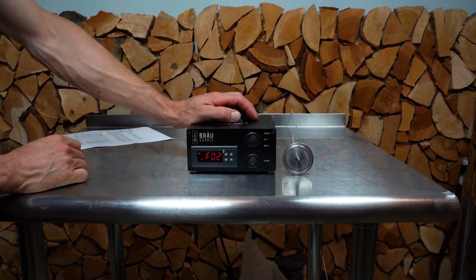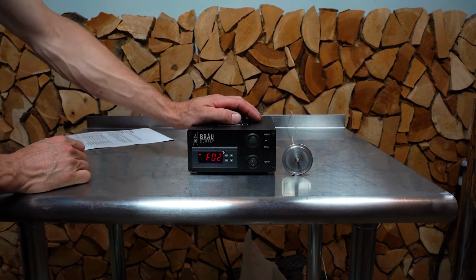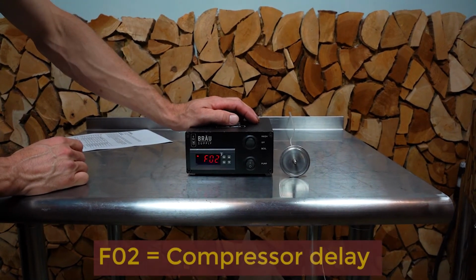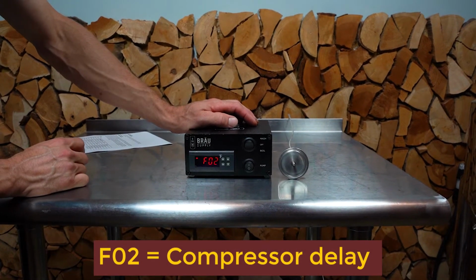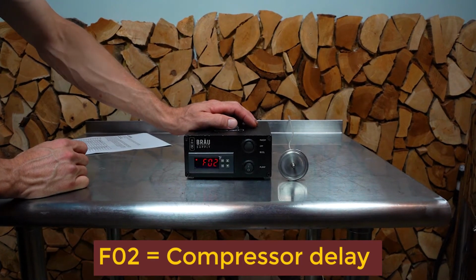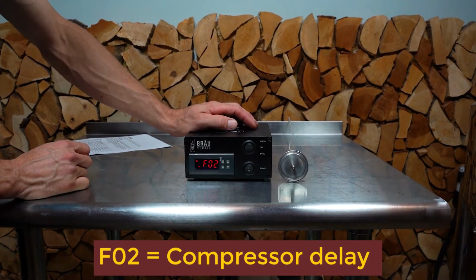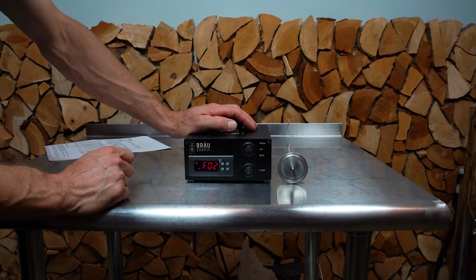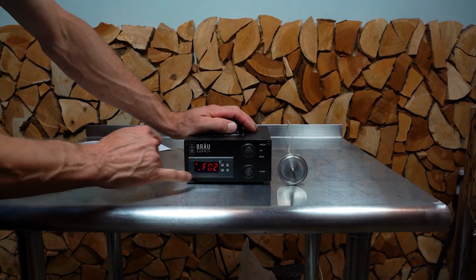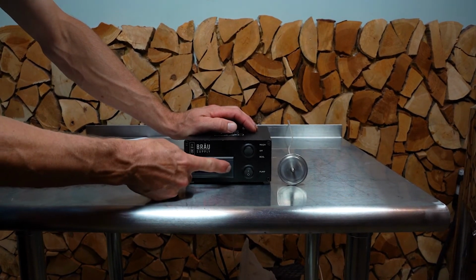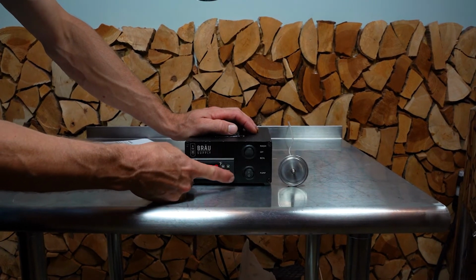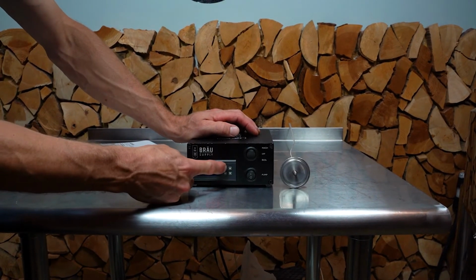Press the up arrow, and now we're at F02. This is compressor delay. Generally not applicable with the Unibrau brewing system, but if you're, let's say, using an air conditioner of sorts or a glycol chiller on the cooling side, you may want to adjust the parameters on F02.